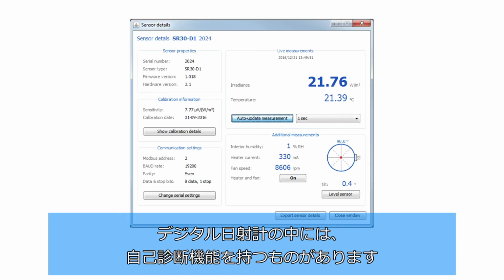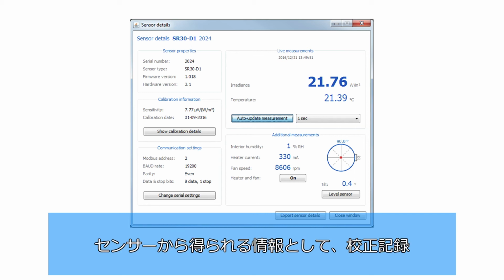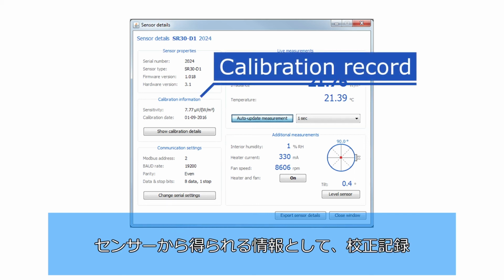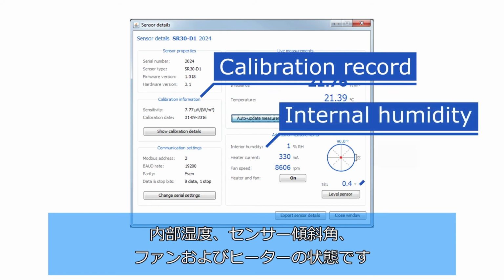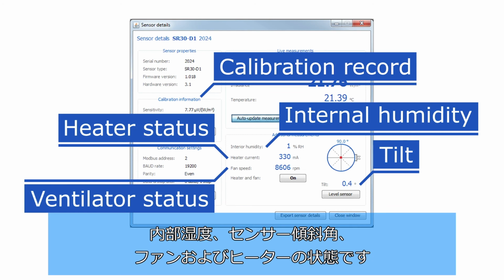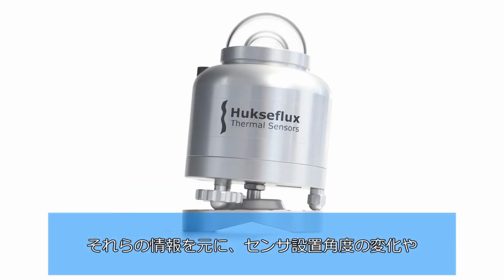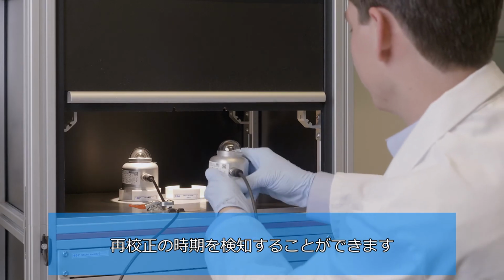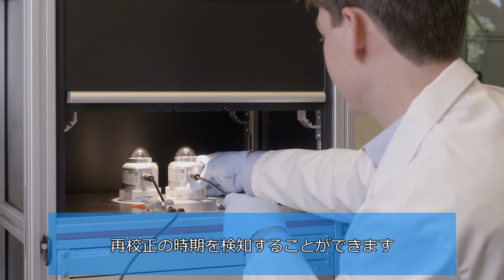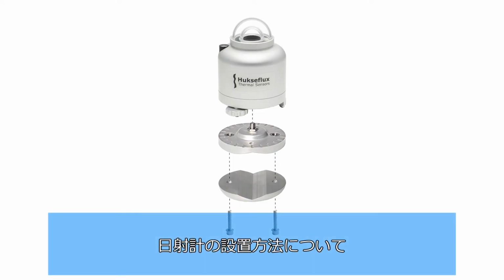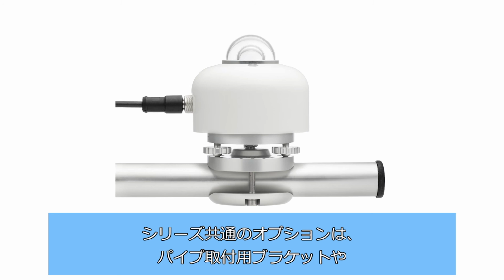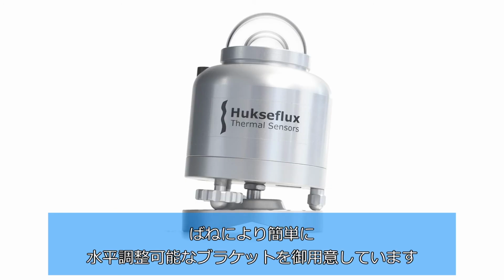Some digital pyranometers have internal diagnostics. These provide information such as a calibration record, internal humidity, tilt angle, ventilator status, and heater status. It can tell you when leveling is off or when it is time to recalibrate. Pyranometers should be mounted. Common options are brackets for tube mounting and spring-loaded connections for easy leveling.